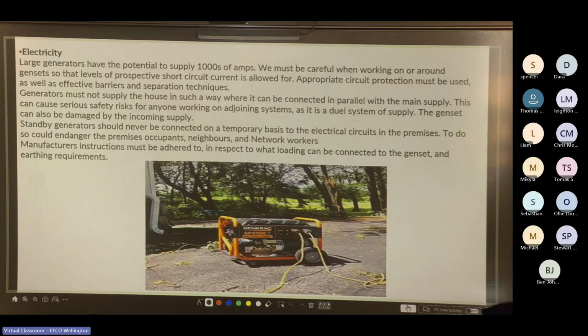Generators must not supply the house in such a way where it can be connected in parallel with the main supply. This can cause serious safety risks for anyone working on adjoining systems, as is a dual system of supply. The genset can also be damaged by the incoming supply. Standby generators should never be connected on a temporary basis to the electrical circuits in the premises. To do so could endanger the premises occupants, neighbours and network workers. Manufacturer's instruction must be adhered to in respect of what loading can be connected to the gensets and earthing requirements.